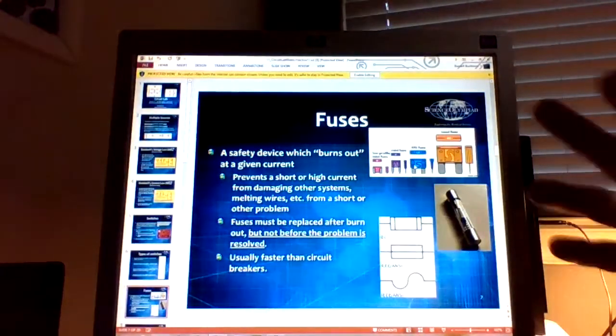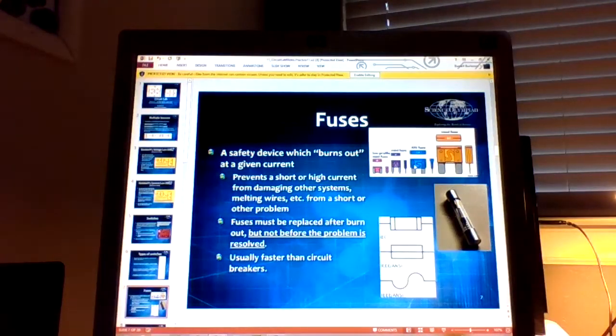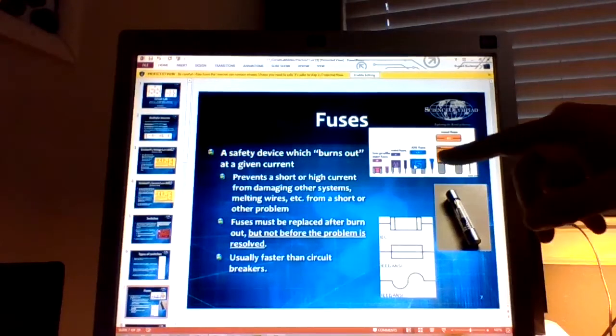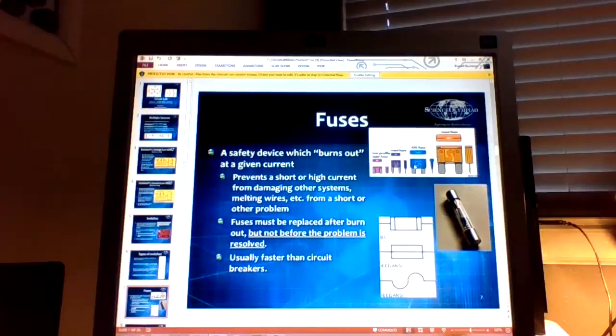So let's say I had a wire rated for 20 amps. I put a 15 amp fuse on it. I never have to worry about melting that wire. The problem is, once it burns, that fuse is done. It's gone forever. First you have to fix whatever caused the overcurrent situation, and then you can replace the fuse.